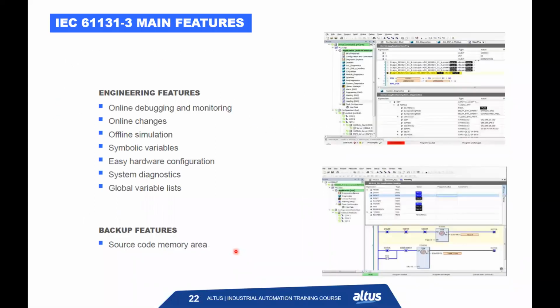Here are the main engineering features in IEC 61131 part 3. If a controller, a PLC, follows this standard, you will see these: online debugging, online changes, offline simulation, symbolic variables, easy hardware configuration, system diagnostics, global variable list, and so on. Of course, there are also backup features; the source code can be stored in the PLC memory too.